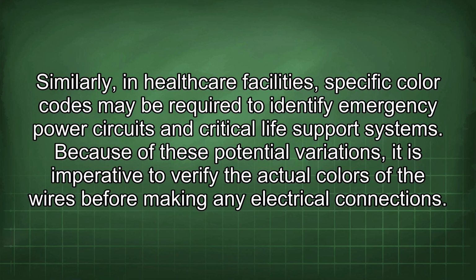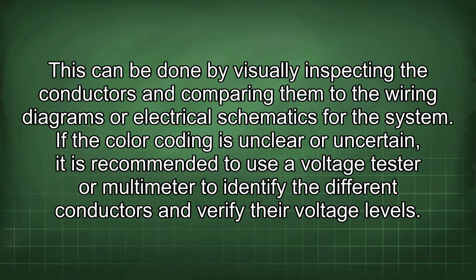Because of these potential variations, it is imperative to verify the actual colors of the wires before making any electrical connections. This can be done by visually inspecting the conductors and comparing them to the wiring diagrams or electrical schematics for the system. If the color coding is unclear or uncertain, it is recommended to use a voltage tester or multimeter to identify the different conductors and verify their voltage levels.